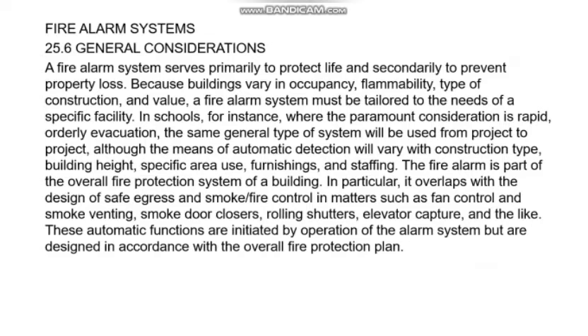In schools, for instance, where the paramount consideration is rapid, orderly evacuation, the same general type of system will be used from project to project, although the means of automatic detection will vary with construction type, building height, specific area use, furnishings, and staffing. The fire alarm is part of the overall fire protection system of a building.